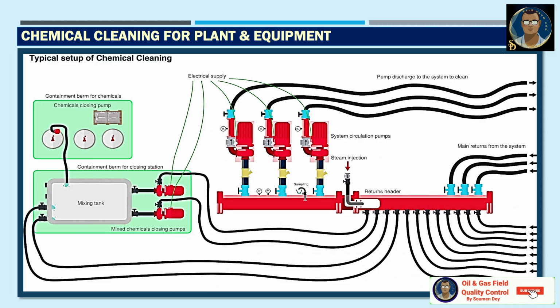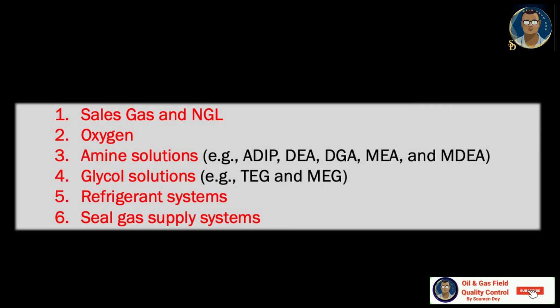The services where chemical cleaning of in-plant piping and equipment is generally mandatory are sales gas and NGL, oxygen, and amine solutions, which are ADIP, DEA, DGA, MEA, MDEA. In the next slides, all these abbreviations of the chemical names are mentioned. You can stop the slide and take a screenshot if you need. For glycol solutions, we also need to do chemical cleaning. Also refrigerant systems and seal gas supply systems.